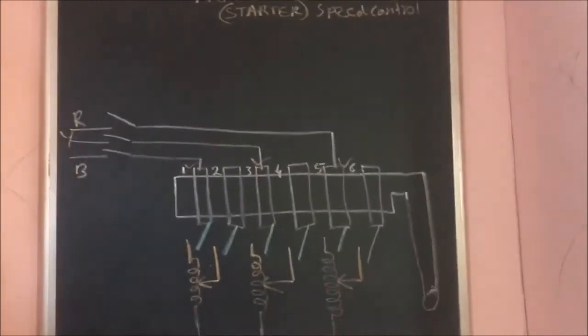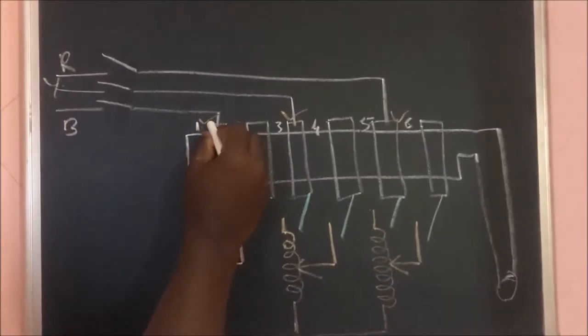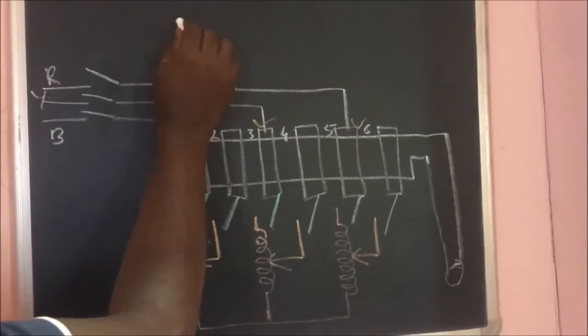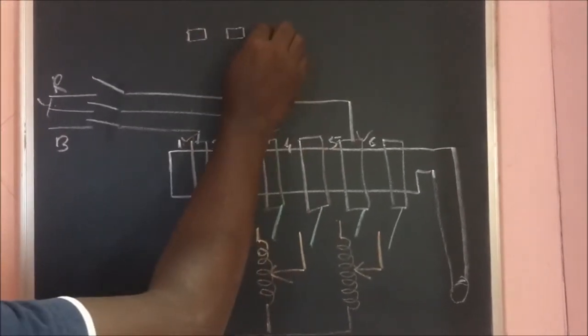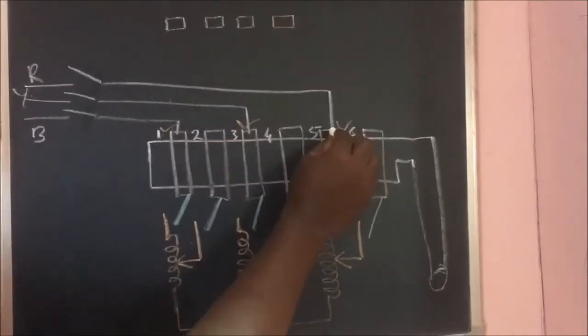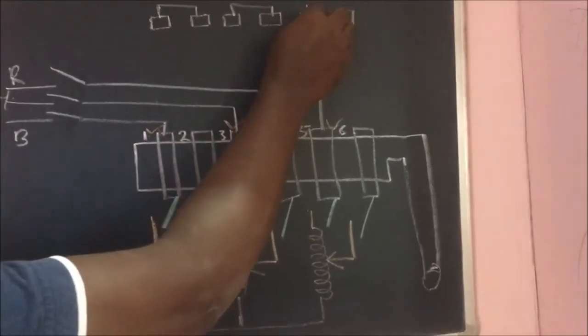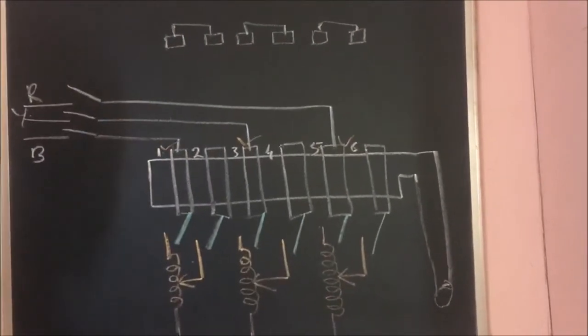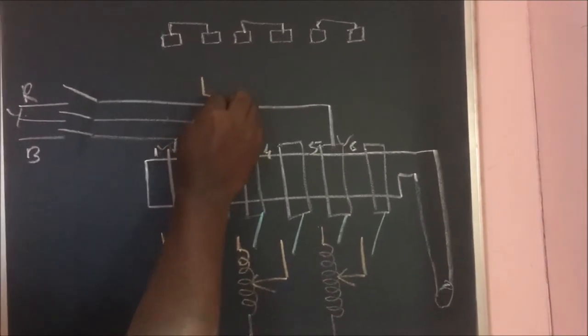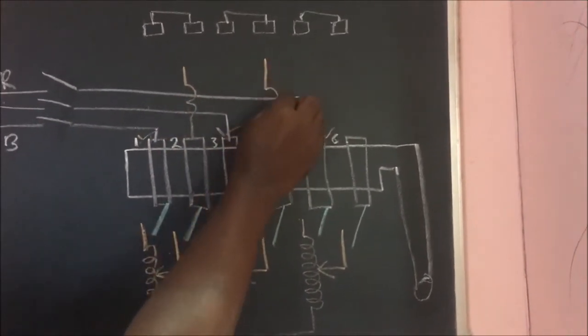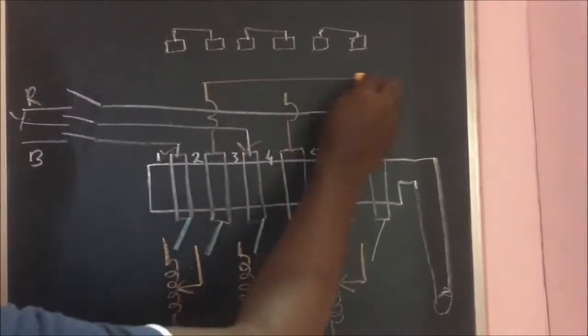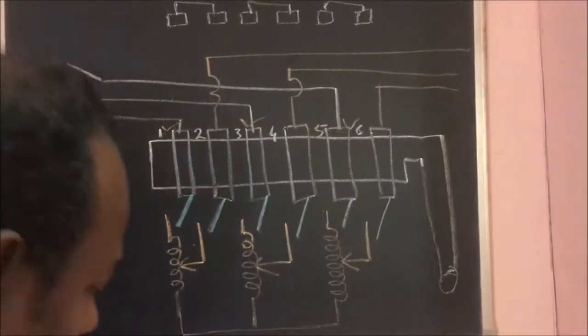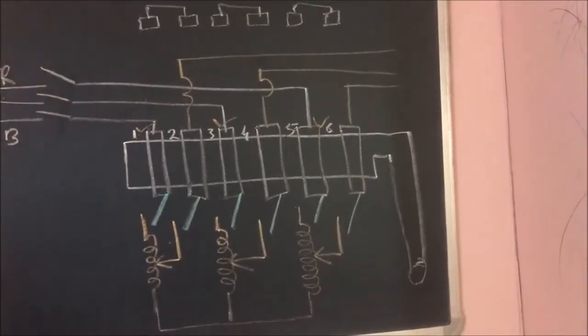First of all, for the odd numbers 1 3 5, on the left side you have to draw the winding as shown in the diagram. Then in the middle of that winding you have to make an arrow mark and connect it nearer to the even numbers 2 4 6 as shown in the blackboard. Then you have to make the three-phase connections. Here 1 3 5 is the input.